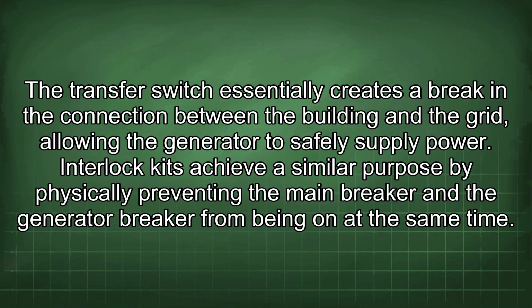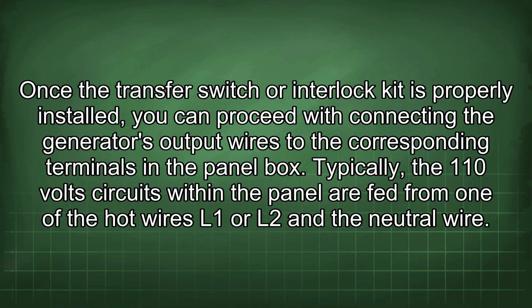The transfer switch essentially creates a break in the connection between the building and the grid, allowing the generator to safely supply power. Interlock kits achieve a similar purpose by physically preventing the main breaker and the generator breaker from being on at the same time. Once the transfer switch or interlock kit is properly installed, you can proceed with connecting the generator's output wires to the corresponding terminals in a panel box.